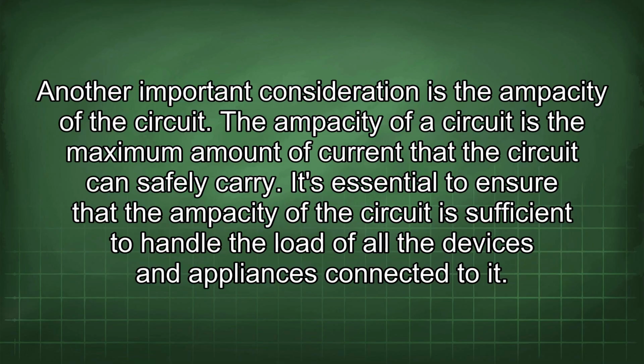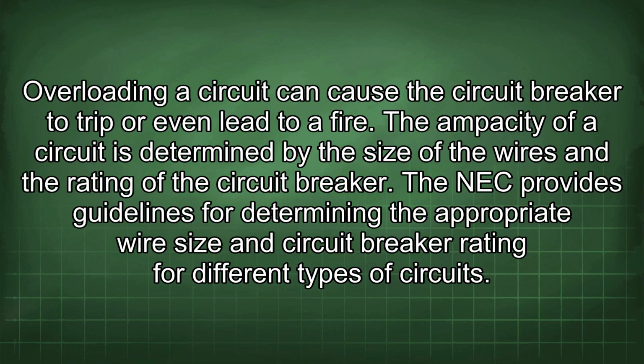Another important consideration is the ampacity of the circuit. The ampacity of a circuit is the maximum amount of current that the circuit can safely carry. It's essential to ensure that the ampacity of the circuit is sufficient to handle the load of all the devices and appliances connected to it. Overloading a circuit can cause the circuit breaker to trip or even lead to a fire. The ampacity of a circuit is determined by the size of the wires and the rating of the circuit breaker.